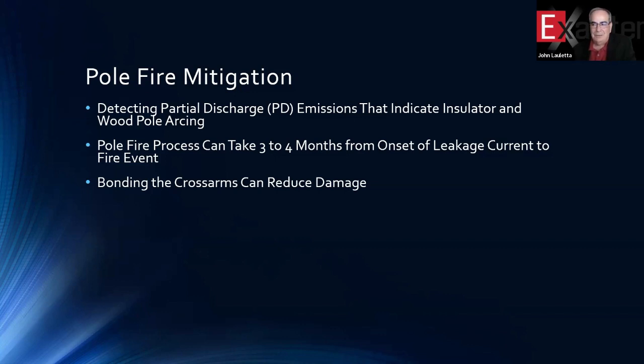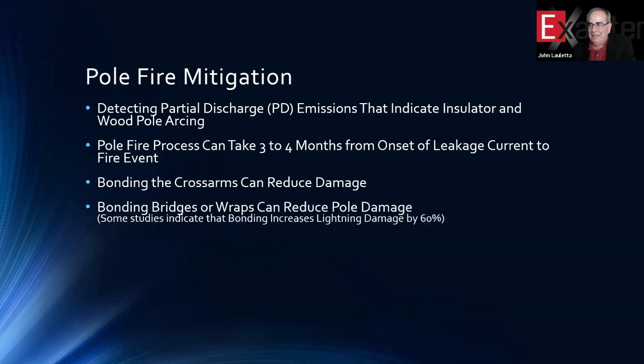Bonding is a technique that some utilities use that can reduce damage. However, bonding raises the ground to the top of the pole. So now you've got a higher stress at just the top of the pole. So you don't have the benefit of that riser from the ground up to the crossarm as part of the impedance of the system to minimize the serial current flow through it. So I don't know. Sometimes some people swear by bonding, others avoid it.